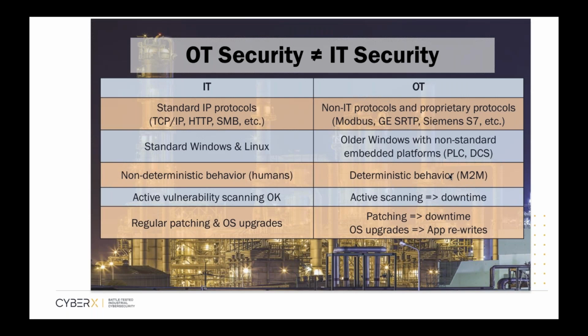And downtime in an OT environment means, at best, loss of revenue. At worst, some sort of catastrophic environmental damage or even loss of human life. So, an OT system is designed to be up all the time. It has to stay up all the time. And for that reason, scanning of networks that is active, either has an agent or is, let's say, querying a device, is generally speaking avoided and has been avoided historically.